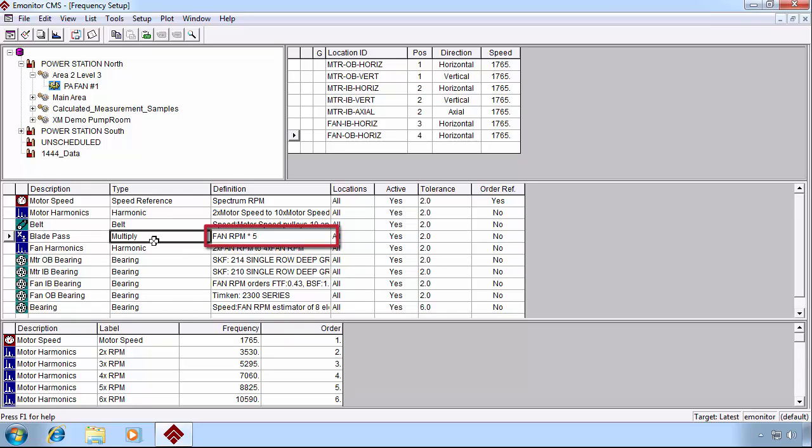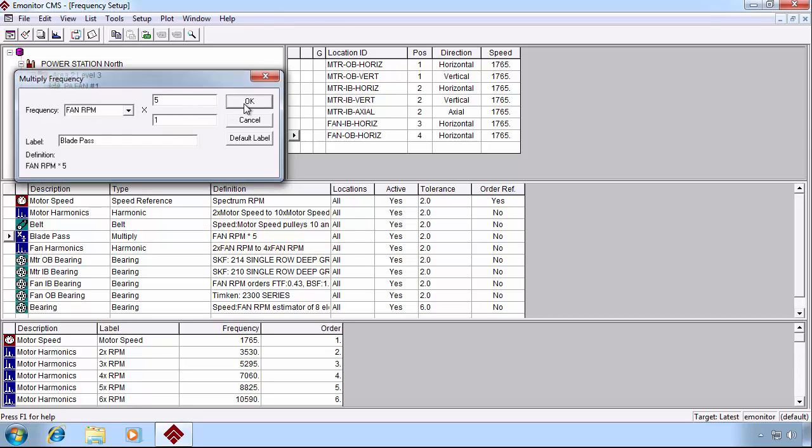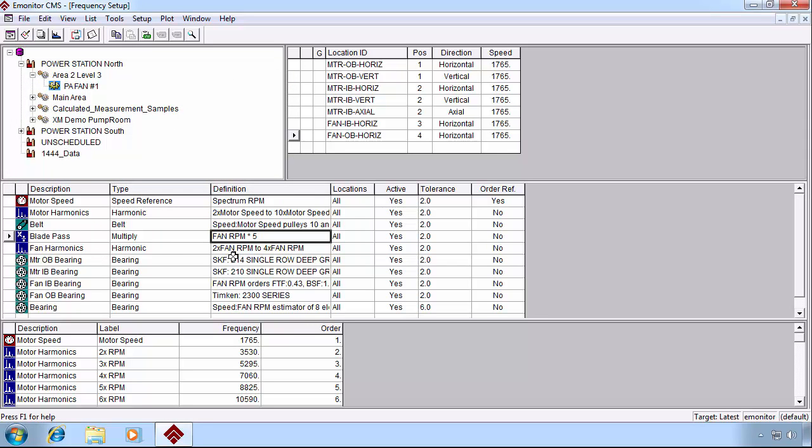Now we might want to know what our blade pass frequency is that we saw on our spectrum. In this case, we've got five fan blades. So we simply add a multiply frequency type based on the fundamental fan RPM, then we multiply it times five. That's our blade pass.